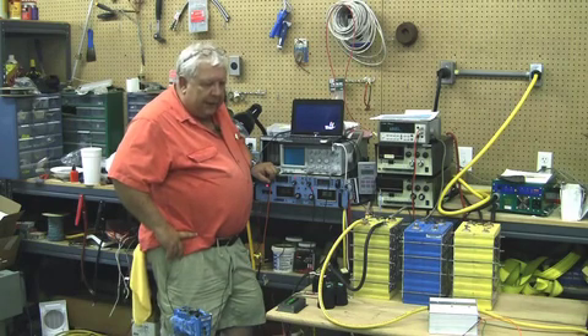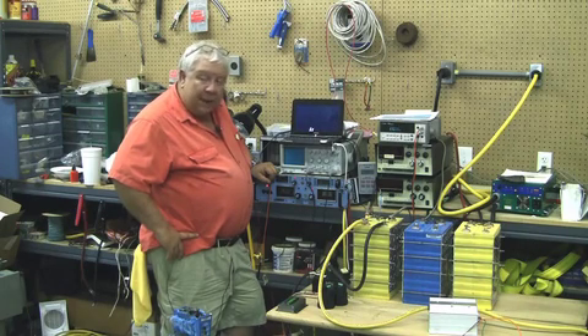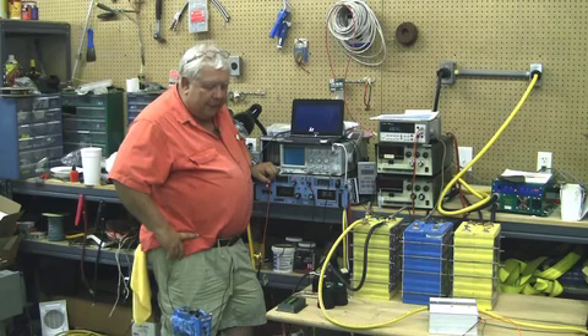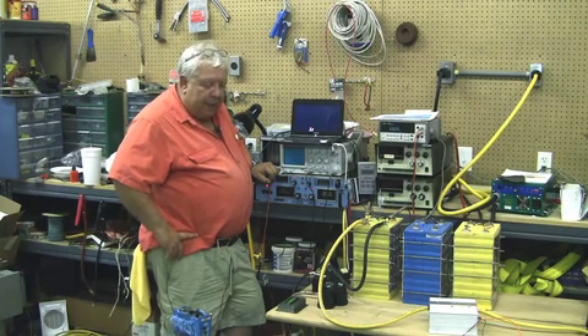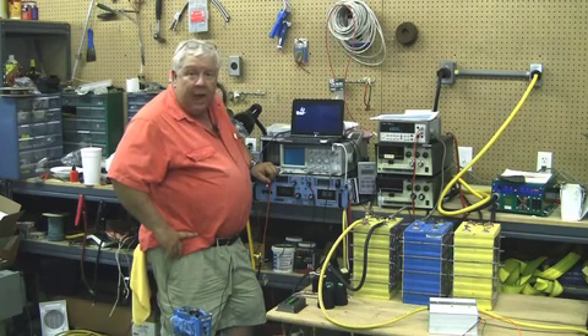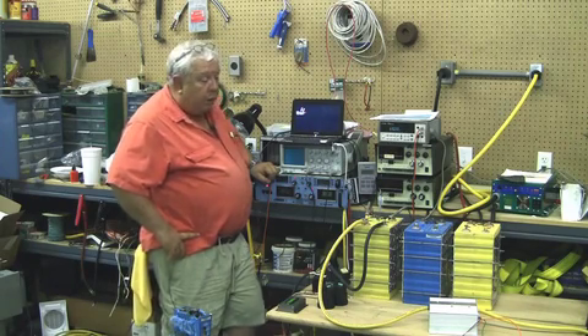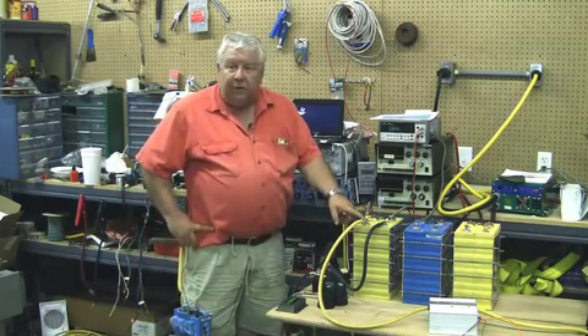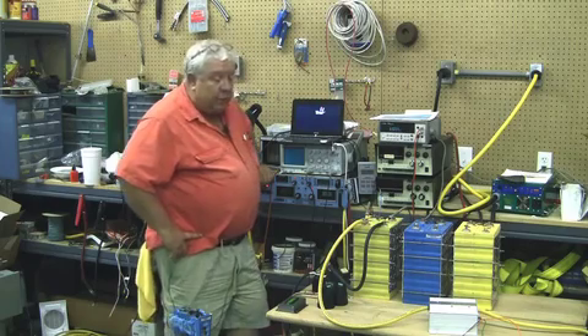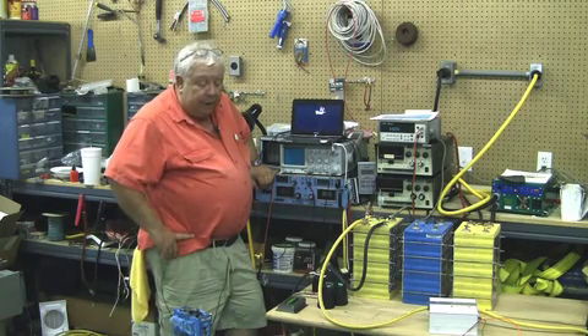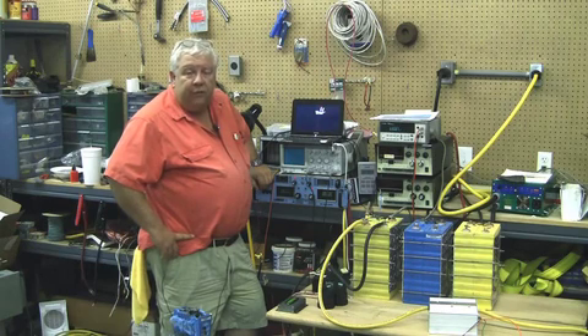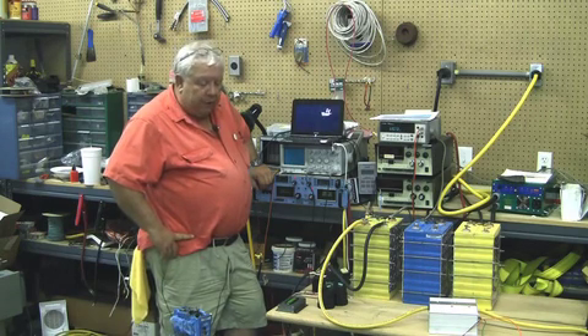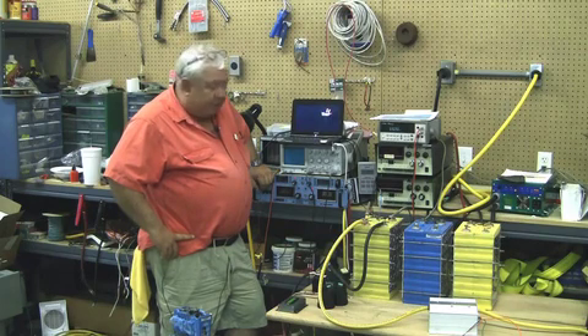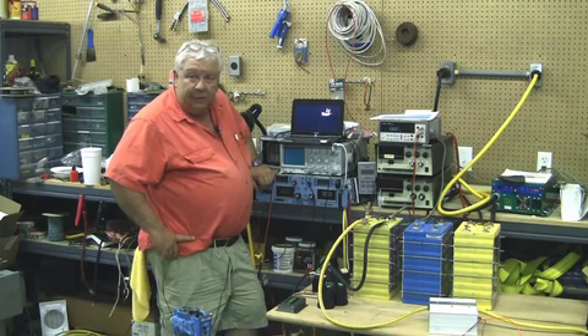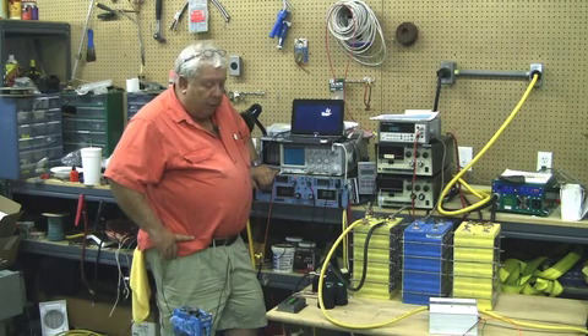There's some indication from the manufacturers - and I don't think they fully know, the way they phrase it, though it kind of makes sense, but I'm not sure they've demonstrated it - that at higher currents, they state you can charge these cells at up to 3C. This 200 amp hour cell, you can put 600 amps in it and recharge it in 20 minutes. They do indicate there's probably some decrease in cycle life doing that, so it's not something you'd want to do every day, but to do it on occasion or semi-regularly, certainly at 1C with a 1-hour charge, would not be a problem.